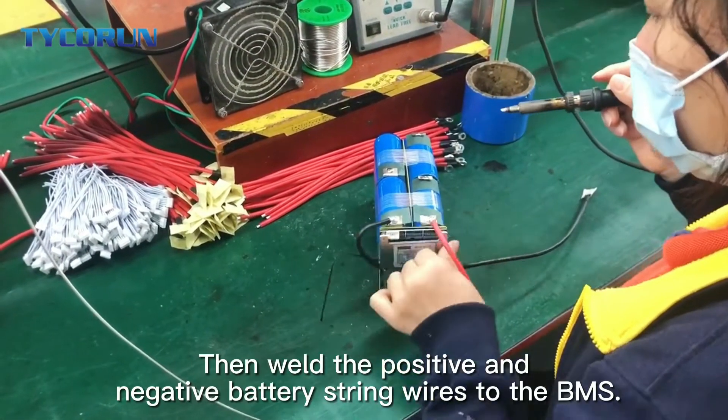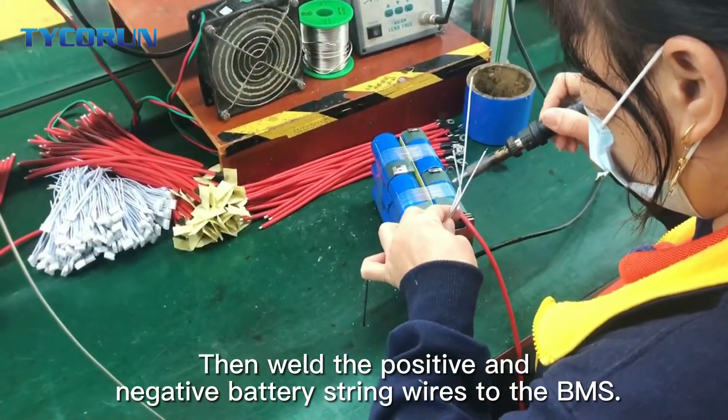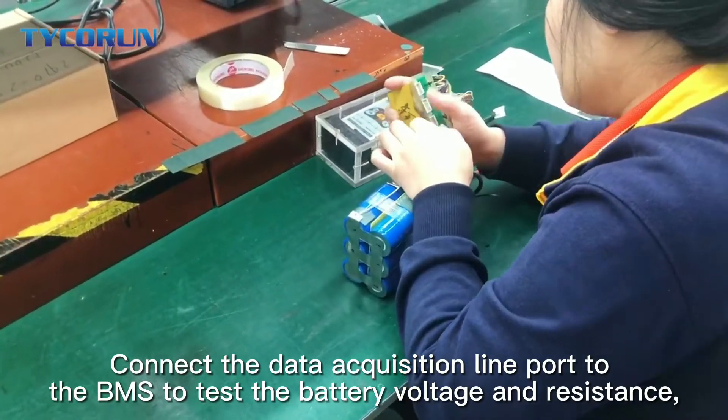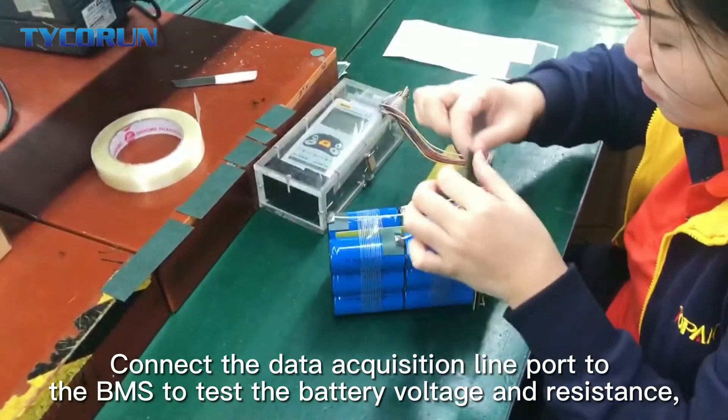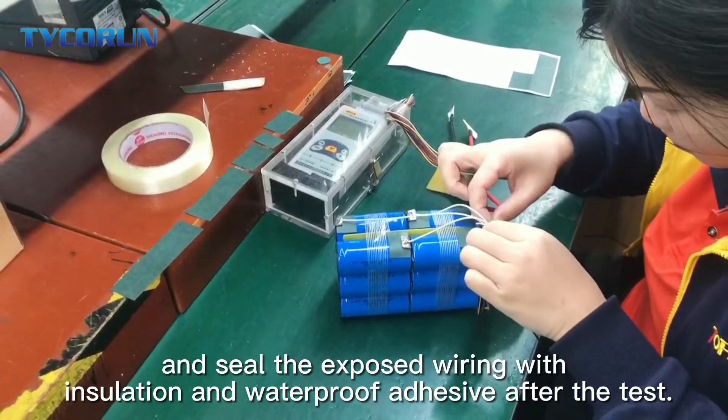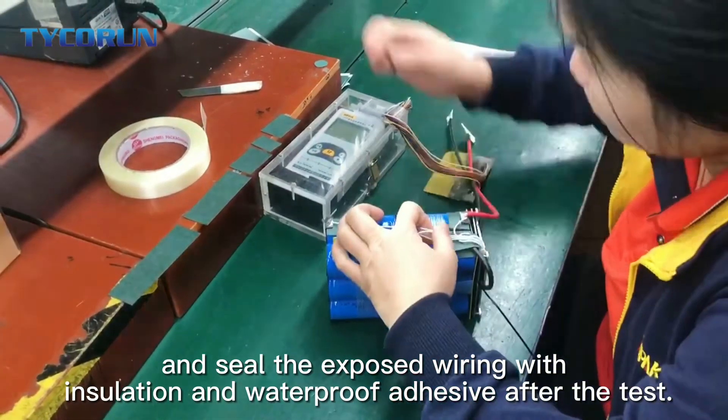Then, weld the positive and negative battery string wires to BMS. Connect the data acquisition line port to the BMS to test the battery voltage and resistance, and then seal the exposed wiring with insulation and waterproof adhesive after the test.